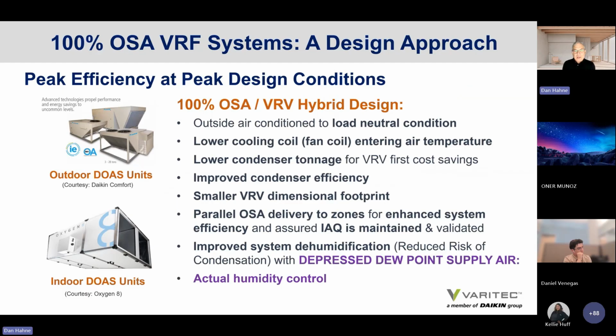The result of doing this is that you provide the outside air at load neutral condition to each independent zone, assuring that the prescribed outdoor air per standard 62.1 is actually reaching each zone. By handling the latent load and the load of the outside air at the DOAS that has an energy recovery component, you have lower cooling coil loads at the fan coil unit, lower condenser tonnage, improved condenser efficiency, and a smaller VRV footprint. And so this offers a lot of reasons to look at a decoupled 100% outside air solution.